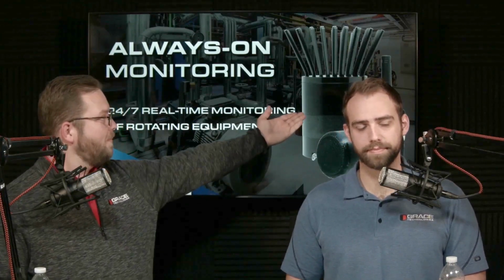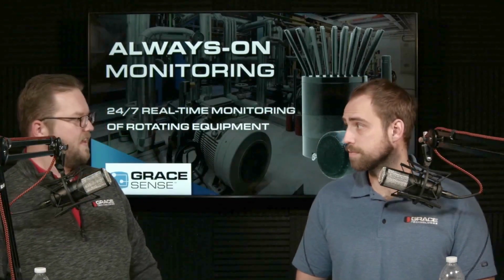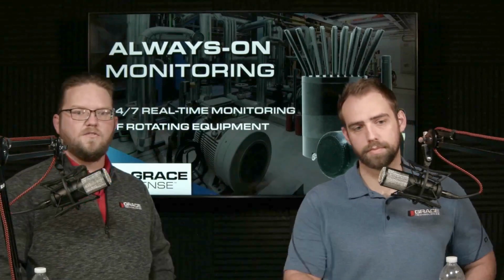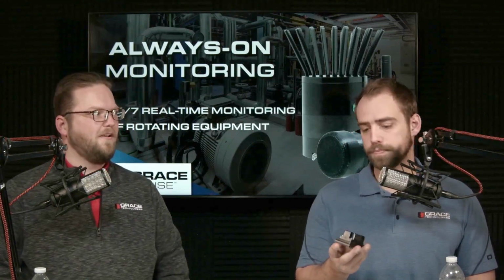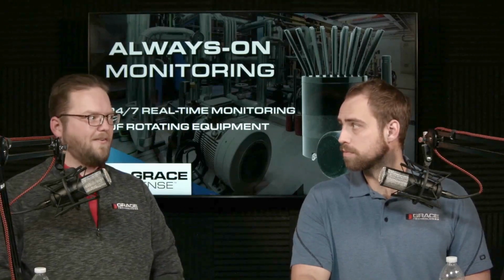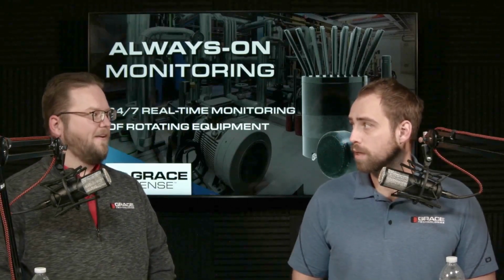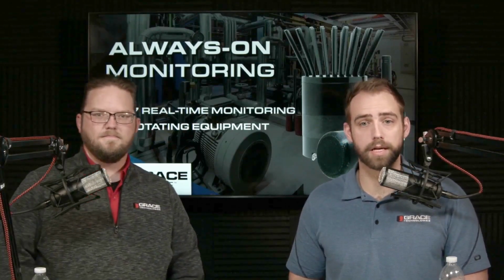A lot of the updates involve the power puck integrated with the vibration node. That enables you to take your power puck with the vibration node built in, place it on a warm motor where you're monitoring vibration, and it will now be powered perpetually. You'll be able to gather vibration data however often you want, never having to go back to wire power or change a battery.